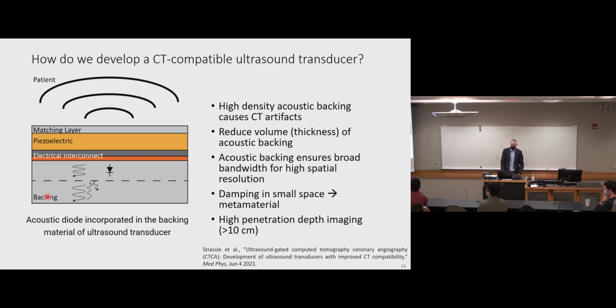For most piezoelectric transducers, the backing represents a large part of the transducer. It represents most of the total volume or the thickness, especially for lower frequency transducers. And so the challenge here becomes, how do we effectively dampen or attenuate this echo in a small space without destroying the CT image? So what we found is, if you look at the different parts of the ultrasound transducer, the part that's not CT compatible is this acoustic backing. And its purpose is it has a high density or a high acoustic impedance similar to the piezoelectric material, so that it's well matched, and the acoustic waves that are in this piezoelectric layer go down into the acoustic backing. Then they're quickly attenuated and they don't travel back into the piezoelectric layer. And we need that because we need a short pulse to give us the high resolution for our ultrasound images.